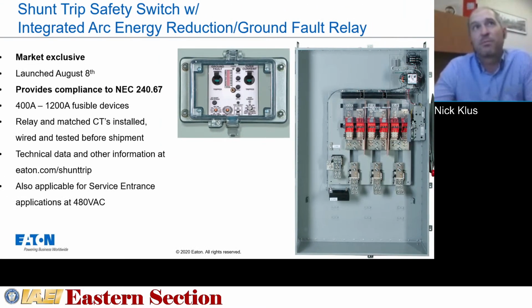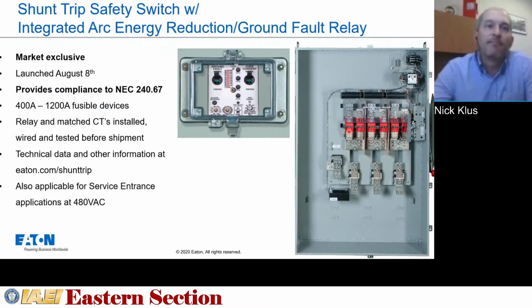Circuit breakers have had shunt trips for years, but if you think about a safety switch product, really the only way to open that product historically had been to walk up to the handle and turn the switch off. So our engineering team, as a first piece of the pie, went to the drawing board and developed, you can see in the gutter there between the handle and the mechanism, a shunt trip mechanism to remotely operate a safety switch.